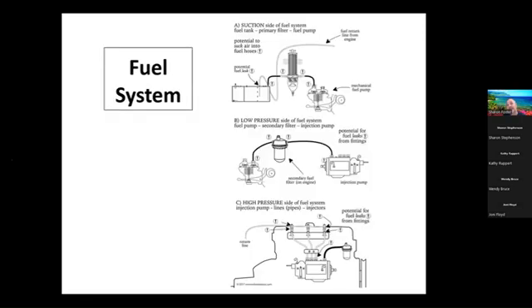All right. Now, that system is actually broken up into three sections. And the reason you need to know the three different sections is because it'll help with troubleshooting. The first section goes from the tank through your primary filter to your mechanical or electrical lift pump. This is your suction side. The reason you need to know this is that if you're running and you start to see air bubbles in the bowl of the Racor, that means you have a leak somewhere and it's pulling air in from outside. That could be the cap on your Racor if you just changed your filters. It could be a bad hose clamp on a hose somewhere. It could be you're running low on fuel, you're bouncing around, and the fuel is getting below the pickup tube. So if you're getting air in the system, more than likely it's coming from the suction side.